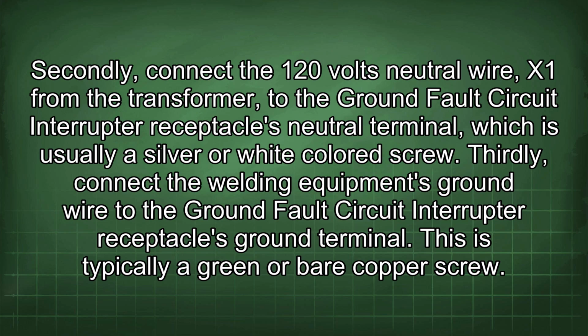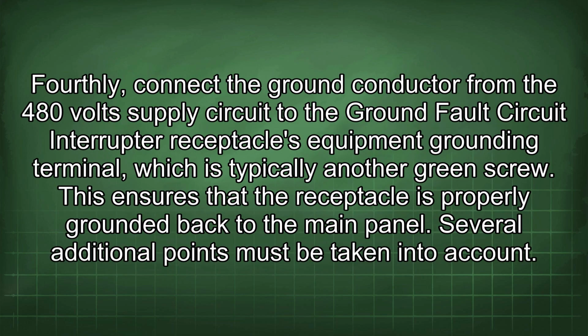Thirdly, connect the welding equipment's ground wire to the ground fault circuit interrupter receptacle's ground terminal. This is typically a green or bare copper screw. Fourthly, connect the ground conductor from the 480 volt supply circuit to the ground fault circuit interrupter receptacle's equipment grounding terminal, which is typically another green screw. This ensures that the receptacle is properly grounded back to the main panel.